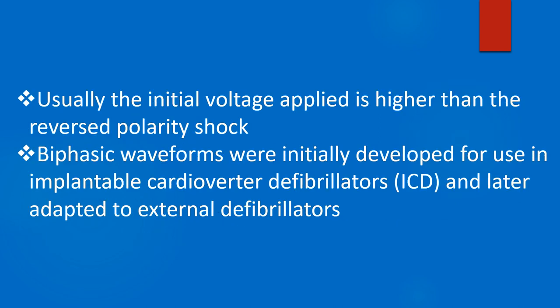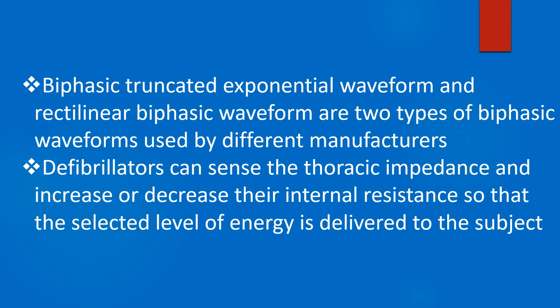Usually the initial voltage applied is higher than the reverse polarity shock. Biphasic waveforms were initially developed for use in implantable cardioverter defibrillators and later adapted to external defibrillators. Biphasic truncated exponential waveform and rectilinear biphasic waveform are two types of biphasic waveforms used by different manufacturers.